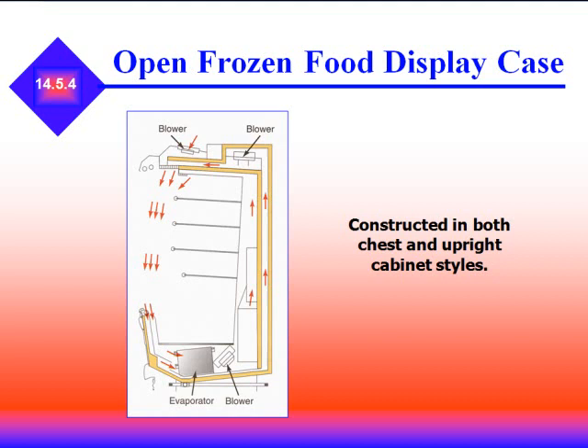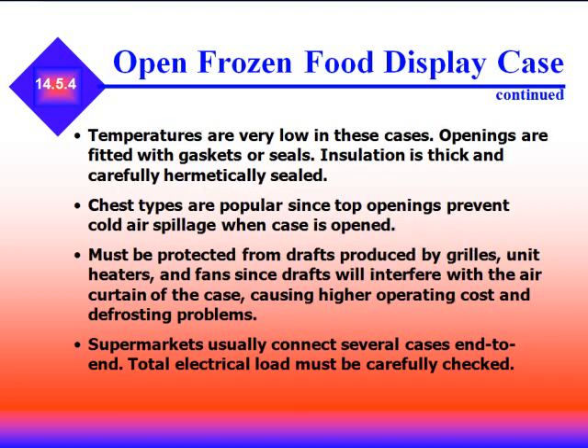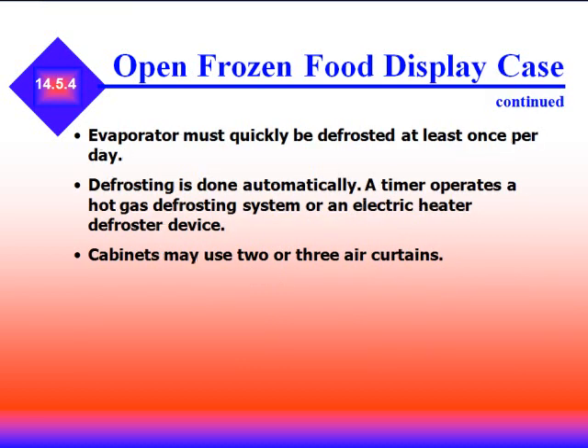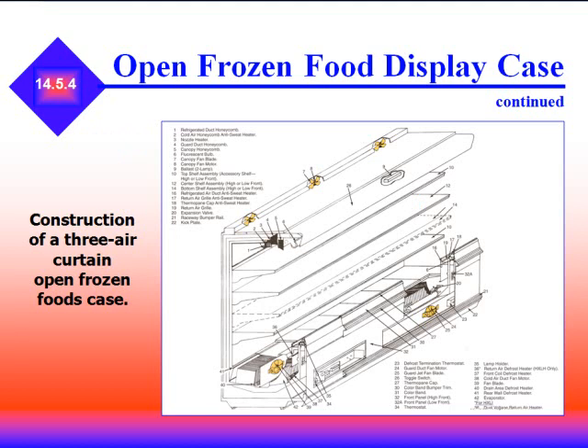Open frozen food display cases are constructed in both chest and upright cabinet styles. Temperatures are very low, openings are filled with gaskets and seals, and insulation is thick and hermetically sealed. Chest types are popular since top openings prevent cold air spillage when the case is opened. Cases must be protected from drafts produced by grills, unit heaters, and fans, as drafts interfere with the air curtain, cause higher operating costs, and create defrost problems. Supermarkets usually connect several cases end to end. The evaporator must be defrosted at least once per day — done automatically using a timer that operates a hot gas defrost mechanism or an electric heater or defrost device.